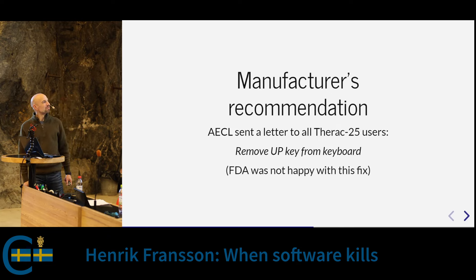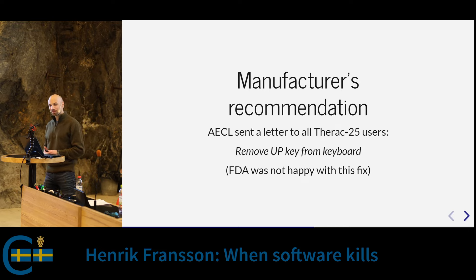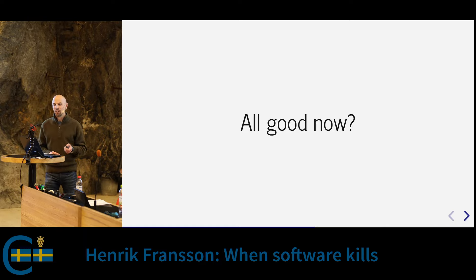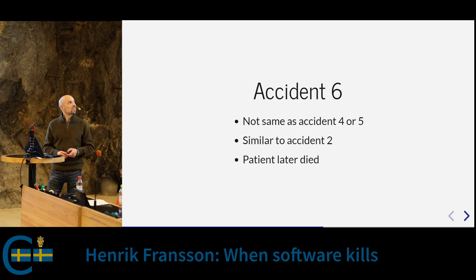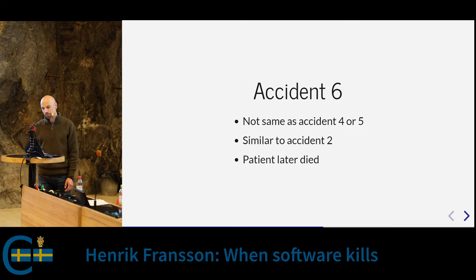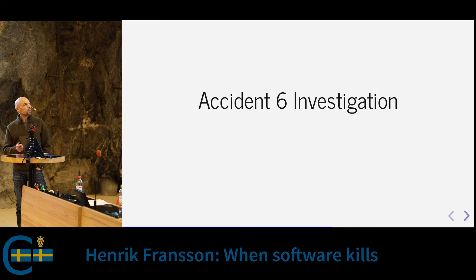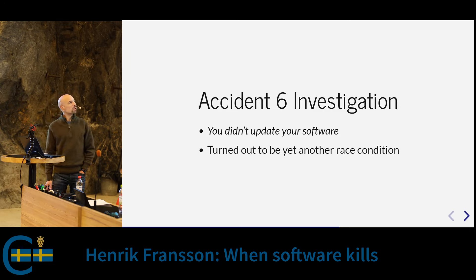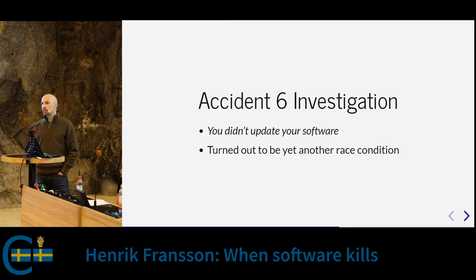They had now claimed a five-orders-of-magnitude improvement and even removed a keyboard key — and yet a sixth accident happened. It wasn't exactly the same as the previous ones, and this patient died. Another investigation started; the manufacturer initially said the hospital hadn't applied the patch, but it turned out this was yet another race condition — a second bug, not the same sequence as before.